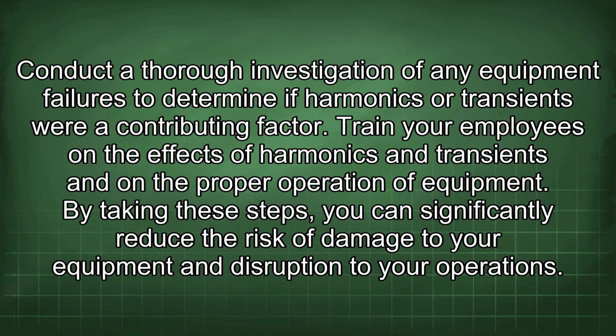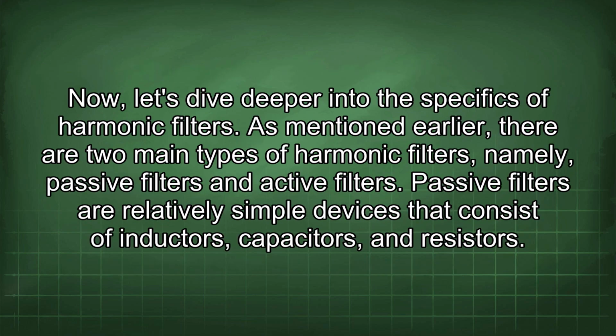Conduct a thorough investigation of any equipment failures to determine if harmonics or transients were a contributing factor. Train your employees on the effects of harmonics and transients and on the proper operation of equipment. By taking these steps, you can significantly reduce the risk of damage to your equipment and disruption to your operations. Now let's dive deeper into the specifics of harmonic filters.